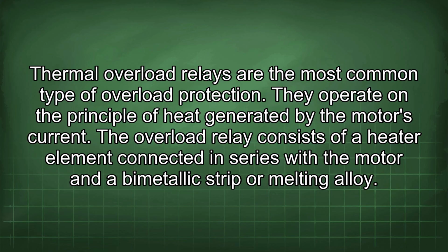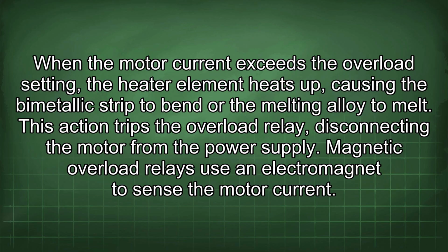They operate on the principle of heat generated by the motor's current. The overload relay consists of a heater element connected in series with the motor and a bimetallic strip or melting alloy. When the motor current exceeds the overload setting, the heater element heats up, causing the bimetallic strip to bend or the melting alloy to melt. This action trips the overload relay, disconnecting the motor from the power supply.